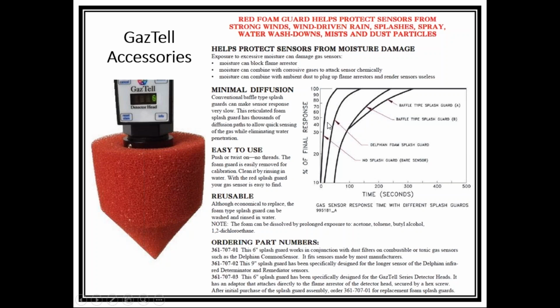If you have to use a guard, you can see that the Delphian guard only adds a slight delay on diffusion of gas. And this is primarily because the actual configuration of the foam is an open cellular foam that allows the gas air to pass right through with little obstruction. And then, of course, when we go to competition, we look at the baffle type splash guards of our competitors, and you can see they reduce, believe it or not, they reduce significantly the speed of response when you put this over the bottom of the sensor.